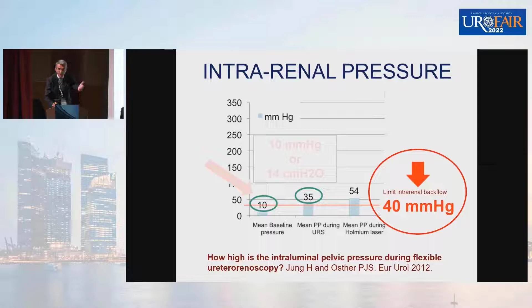Since we irrigate, the pressure increases in the kidney, and most of the time when we do flexible ureteroscopy, the pressure in the kidney is more or less 40 millimeters of mercury. But if you increase the flow by using a pump, or a manual pump, there is a big risk of increasing the pressure in the kidney, up to 3 meters of pressure. Remember the renal colic, it's 1 meter. If you force a manual system or pressure pump, it's possible to generate very high pressure.